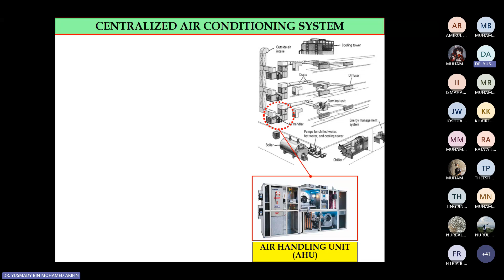So the AHU will be used to change the condition of a room. For example, for this schematic diagram, at the basement of the building, we will have a chiller system and also a boiler system, where the boiler will provide the hot water and the chiller will provide the cold water. Hot water is for the heating process, cool water for the cooling process.